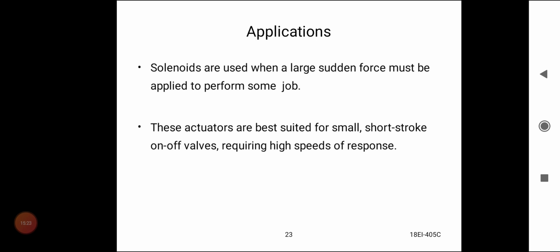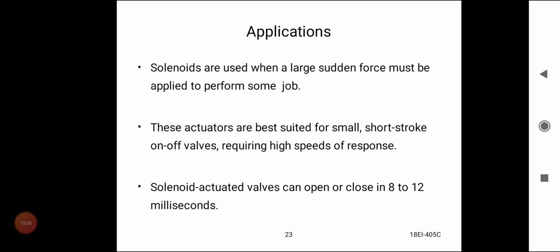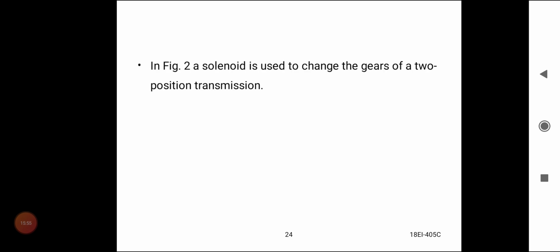These actuators are best suited for small, short stroke on-off valves requiring high speeds of response. Solenoid actuated valves can open or close in 8 to 12 milliseconds.